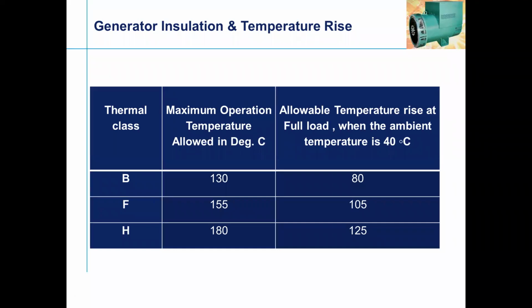If you are going to set any temperature sensors, that means for winding temperature, you keep monitoring it. So there should be a tripping circuit where the temperature can be set, so that any temperature rise of the winding can be determined. Like F class, again, the maximum allowed temperature is 155 degrees, and the maximum allowed temperature rise is 105 degrees. So here we have to consider the ambient: ambient 40 plus 105, which is 145, is your temperature setting, which you can give for a trip. This would say that in case the temperature rise of the winding goes beyond 145, the controller has to trip. So this is fundamentally information for the customer and the commissioning engineer, as well as the operation and maintenance engineer, to follow this setting on the parameters.